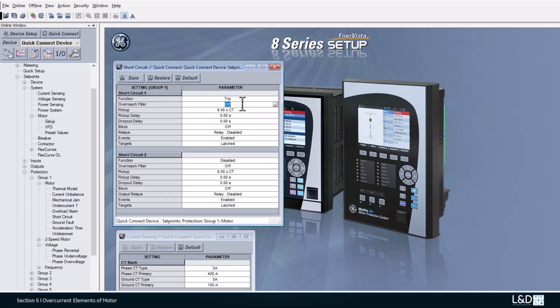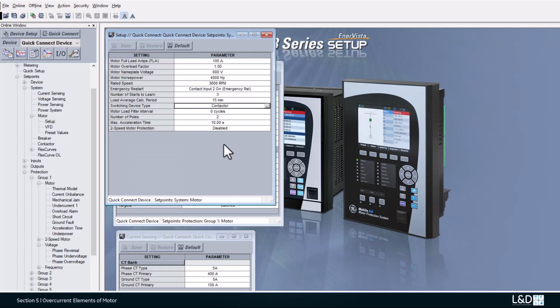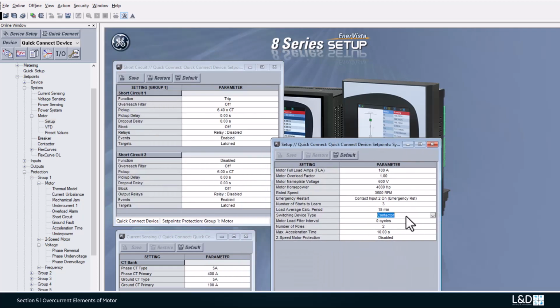The overreach filter function removes the DC component from the asymmetrical current present at the moment of the fault. This eliminates overreach, however, the response time slows slightly, by up to 15 milliseconds. For the interrupting device, when it's set to contactor, it's not rated to break the short circuit fault current. Then this function should not be set to trip and instead should be set to alarm or latched alarm, and an auxiliary relay assigned and connected to an upstream device which is capable of breaking the fault current.